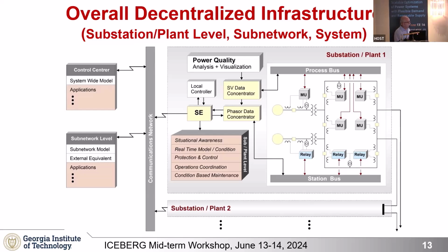Think about the new system, which we refer to as the digital substation. It has two concentrators of data — one for sample values, the other for phasor data — and any application can access these concentrators to get the data it needs to run. It's a very simple process, and this can be expanded from the substation level to a subsystem level, to the full system level, and so on.